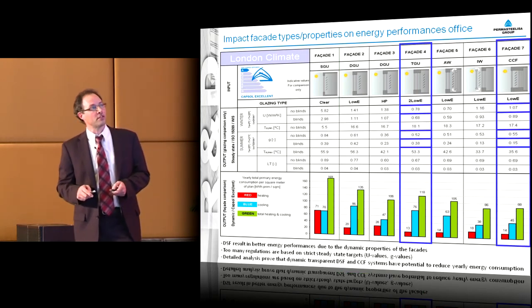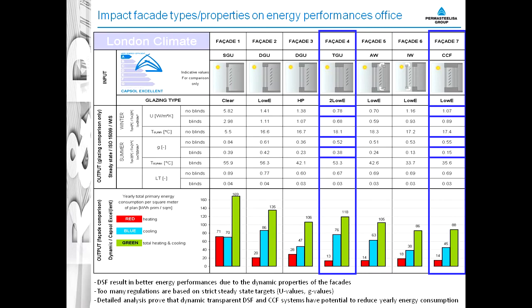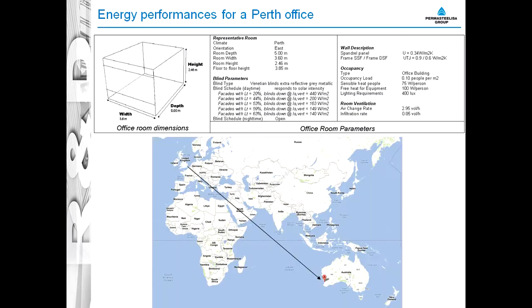Now, a lot of specifications are written for U value - lower the U value as much as possible. You can see here that the U value of a triple glazed unit is better than that of a closed cavity facade, but the energy performance is worse. This is because when the blinds are closed, the solar heat gain coefficient, or G value, is much lower for a closed cavity facade than for a triple glazed unit.